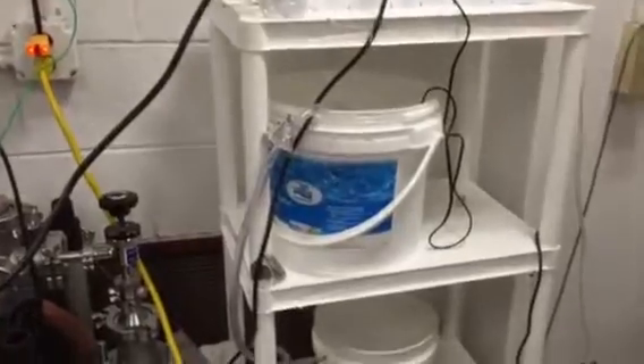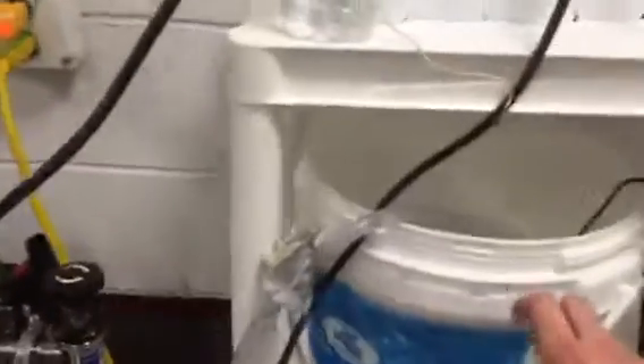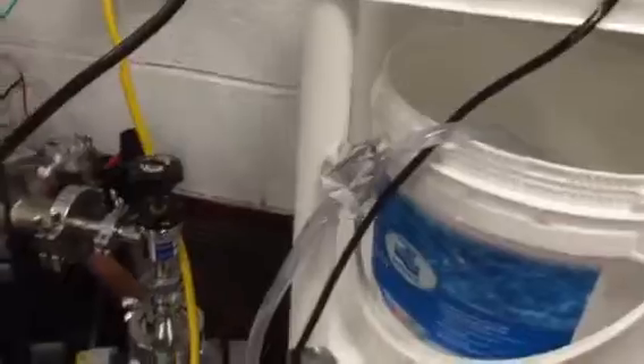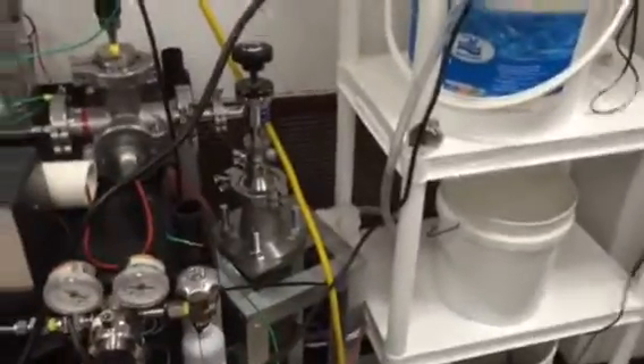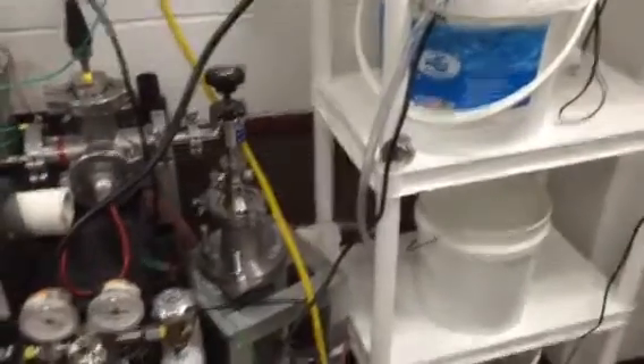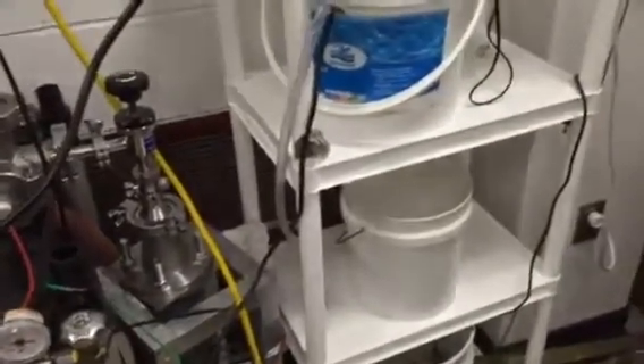Lastly, for water cooling, we have a water-cooled diffusion pump, and right now we don't have a water chiller, but we are using a series of buckets and aquarium pumps to supply the diffusion pump with water between the temperature range of 60 to 80 degrees Fahrenheit.